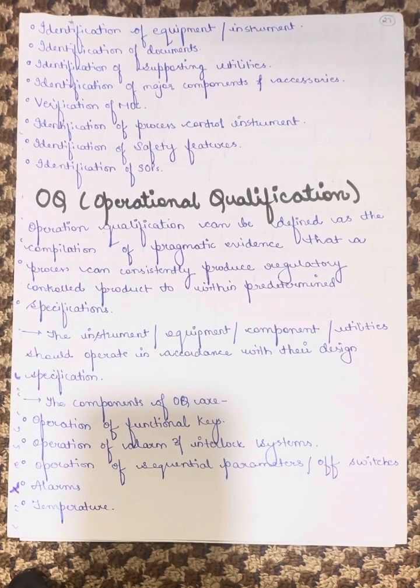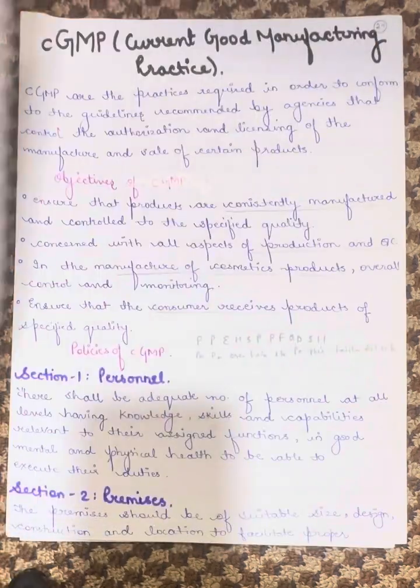We have Operational Qualification. OQ can be defined as the compilation of pragmatic evidence that a process can consistently produce a regulatory controlled product within pre-determined specification. The instrument, component and utility should operate in accordance with the design specification. Components of OQ are: operation of the functional keys, alarm, interlock system operation, operation of sequential parameters or the off switches, alarms, and the temperature that is to be maintained.